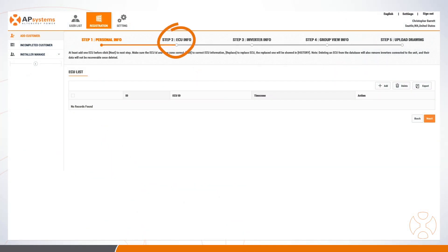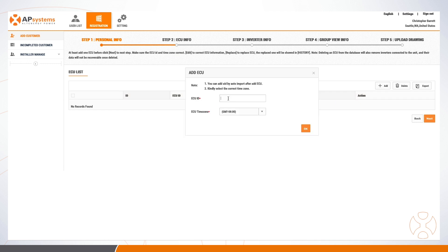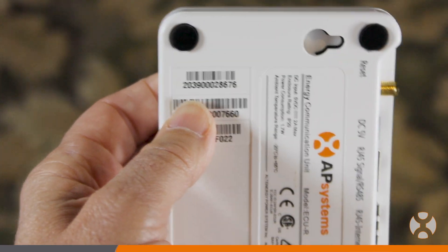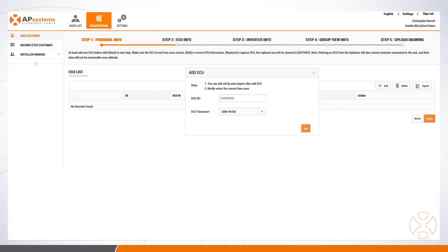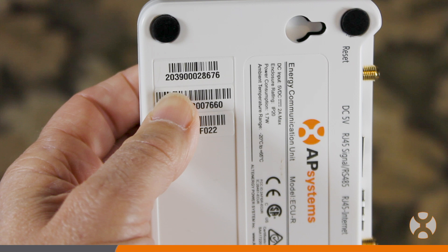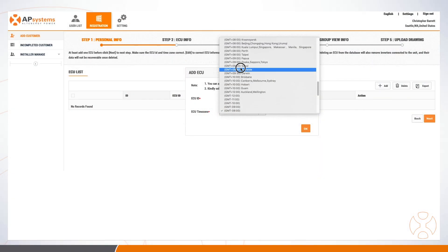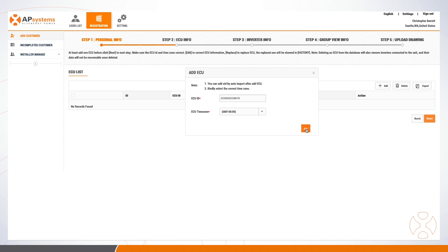Next, the installer adds the ECU UID number from the recent installation by clicking the Add button on the ECU Info step. The installer then enters the 12-digit ECU UID, which is the topmost barcode located on the back or bottom of the ECU, typically beginning with a two. Take care when entering this number, as an incorrect ECU number entry will not enable communication with the site. Keep in mind that this is not the device IP address but a unique serial number assigned by AP Systems. Enter the time zone and click Next.